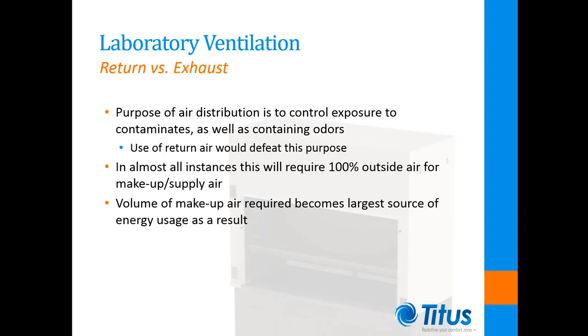Providing 100% outside air can be extremely costly. First, the air must be dehumidified to meet space humidity requirements and then supplied to the space at the correct temperature. Depending on the conditions of the space, this might also include zone reheat to prevent overcooling. As a result, in laboratories where makeup air is driving the ventilation requirements, the amount of air required to ventilate and condition the space can lead to extreme levels of energy consumption.